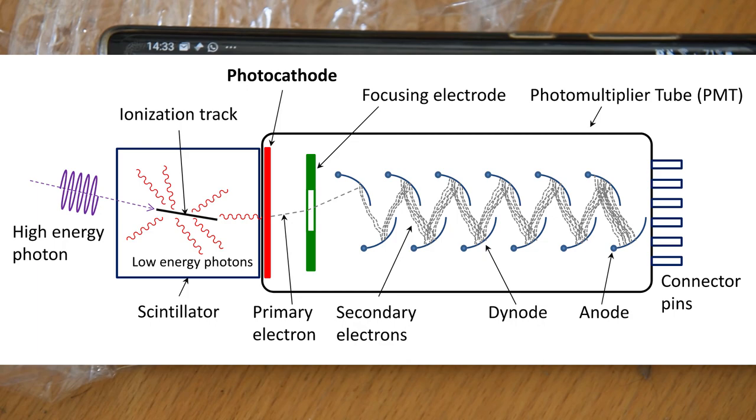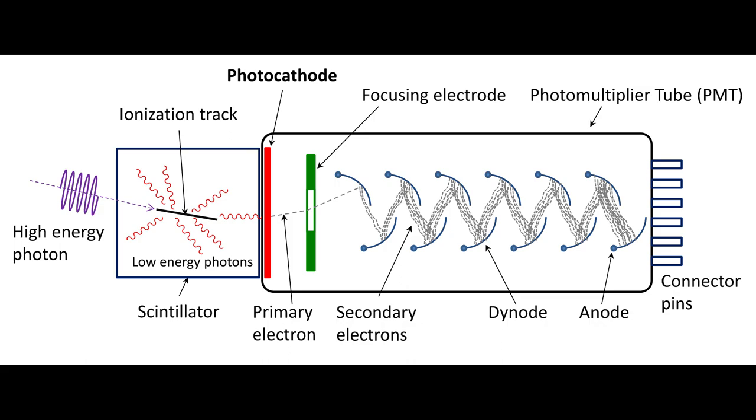Let us return to the picture and remember that the scintillator produces pulses with sizes that correspond to the incoming photon energy. But this is only true if all the energy from the photon is deposited in the scintillation crystal. If part of the energy can escape the crystal because the photon didn't scatter enough or the crystal just wasn't big or dense enough to stop it, that means that part of the information was lost.